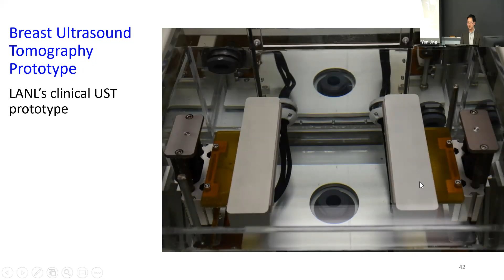And here is a picture of the system we put in the hospital for the patient study. The electronics are put behind, and the patient only sees this table, while the master computer controls the data acquisition. The system we built has a total of 768 transducer elements with 384 parallel receive channels, so we use multiplexing. The distance between the two transducer arrays is adjustable to scan different sizes of breast. And the transducer array translates vertically to scan the whole breast. As I mentioned, the center frequency we use is 1.875 megahertz, and we acquire synthetic aperture ultrasound reflection and transmission data.